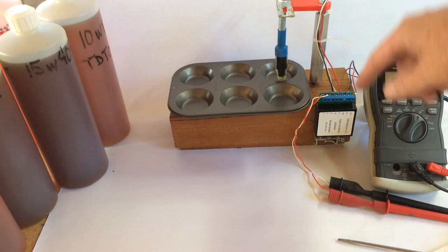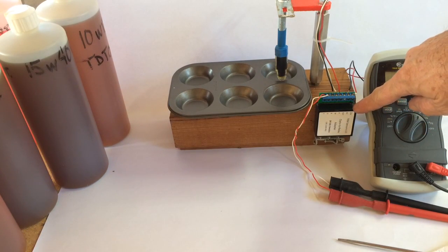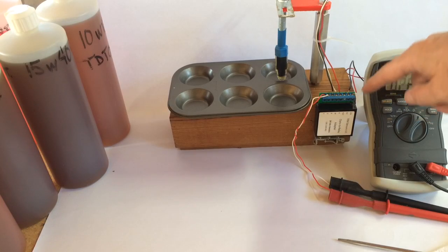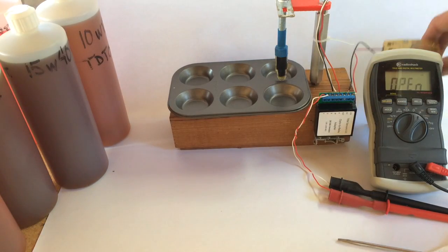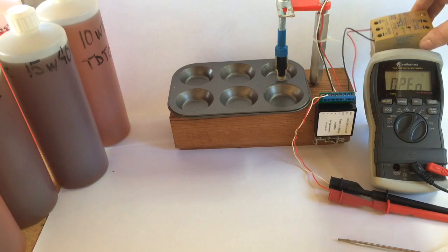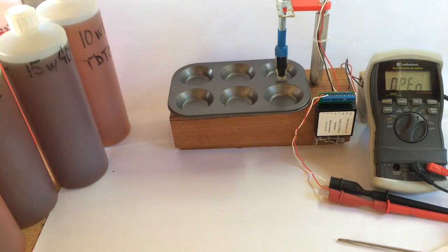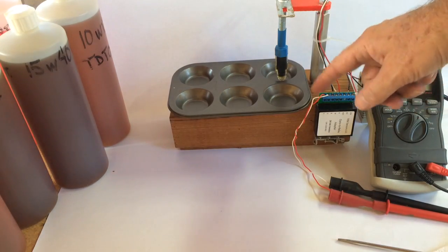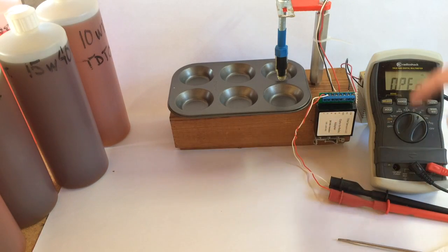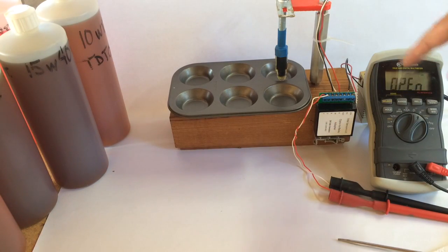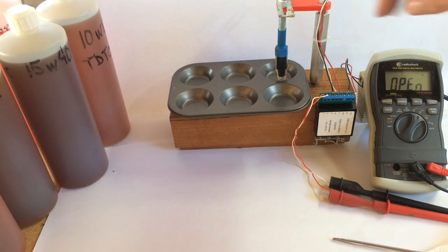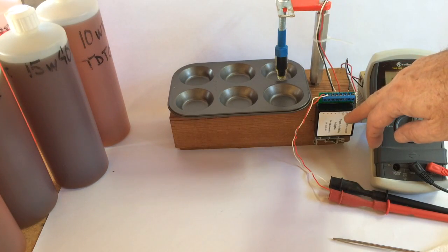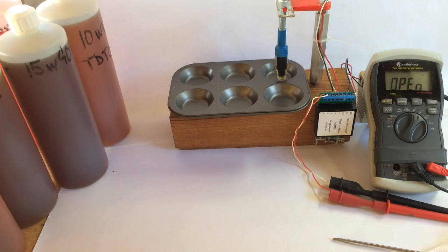There's a 3-wire connection to the optical to relay converter circuit manufactured by TRM. This particular version is running on 24 volts DC. There's also a 12 volt DC version available. And the output is a simple dry contact. It's hooked up to this meter, which will, if we do make detections, go from the word open to the word short, and you should hear a buzzer. So the components of the system really are just the probe and the adapter circuit. Output is a relay contact, input is 12 volts.